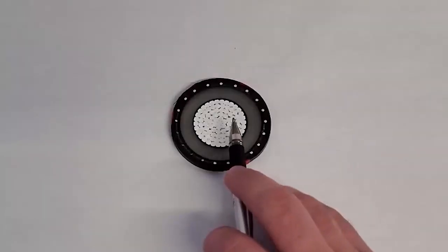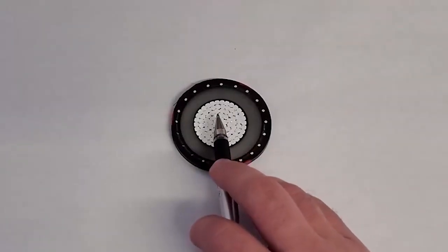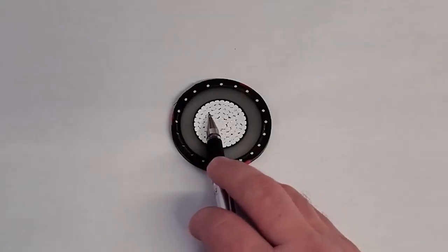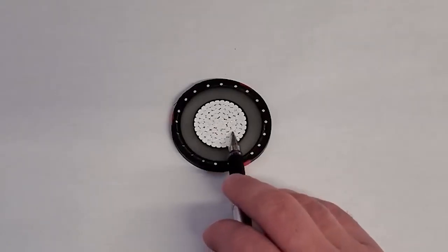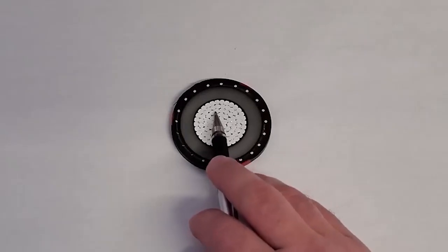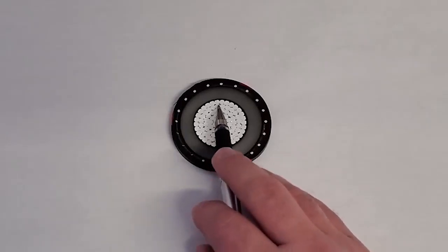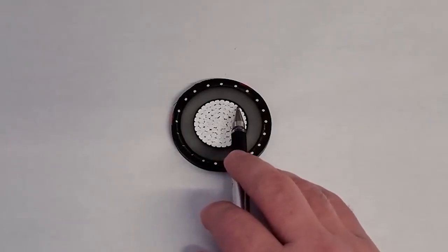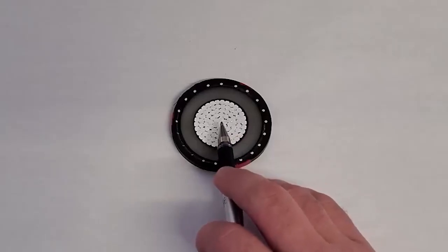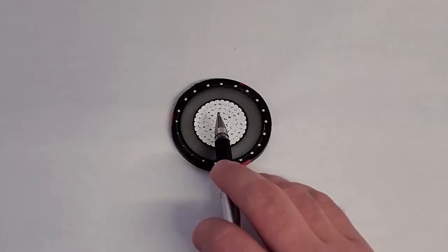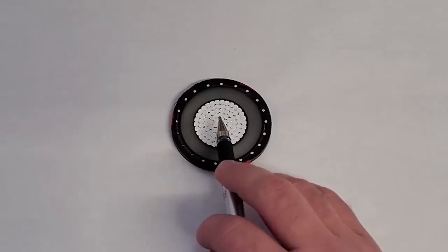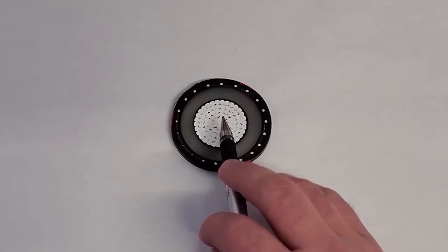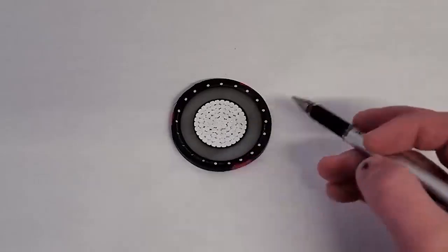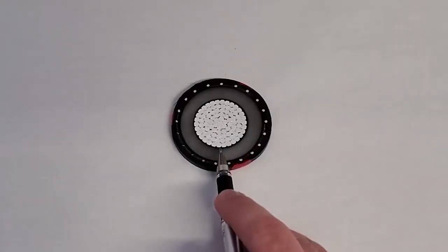So really the name of the game is to keep this as malleable as possible for easy installation, but have as few air gaps here as possible, because that's just inefficiency and losses. And that also causes flux on this outside ring that we'll talk about next. So that's the conductor. Again, copper and aluminum. The main ones that you see in cable like this for wind farms, it's usually always aluminum just because of the cost offset. The next layer is the conductor shield.